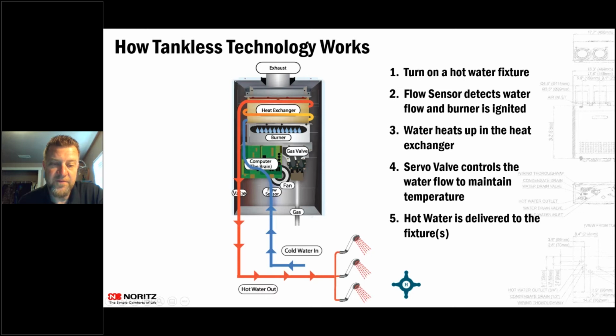So with that valve control here, that valve is doing two different things. One, it's regulating how fast the water is going through the unit so we can stay at temperature, and two, it's tempering that water back down to keep it at temperature so we do not have any water hotter than the set temperature leaving that unit.